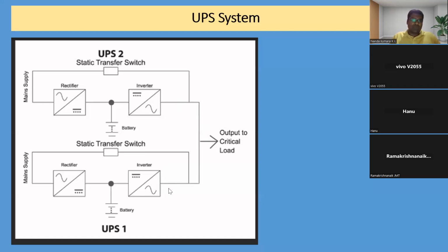Any one UPS will act as a master, and the others as slaves, which keeps monitoring the output data of all three UPS and syncs accordingly. Otherwise, the parallel operation will not happen. It may even trip the UPS. Then the output panel is a single panel, and from there the output feeders are taken out.